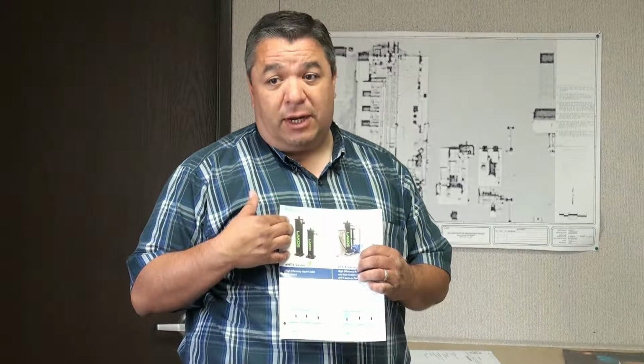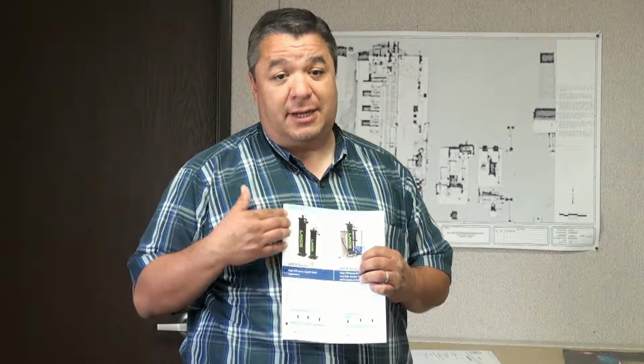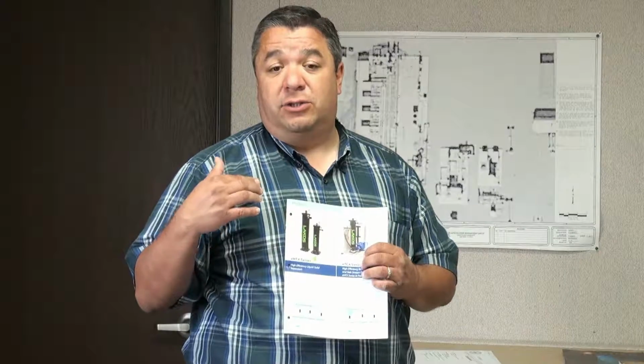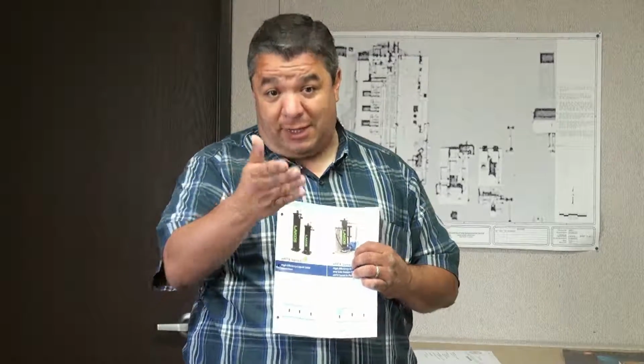So you have a separator in your cooling tower, your tower's going to last a lot longer, it's going to have a lot less problems. Your fill is going to last a lot longer with fewer problems. Your chiller's going to have a lot less problems too, as long as you maintain the bags.